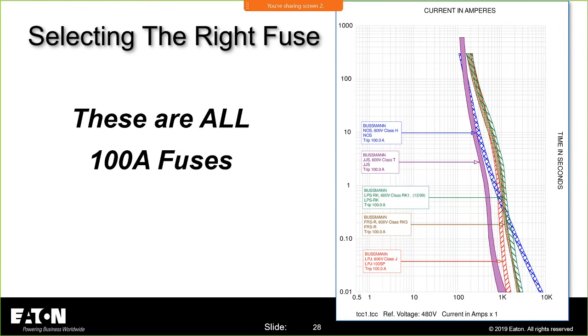All right, so let's take a look. These are all 100 amp fuses, and you're going to say, wow, those are all rated 100 amps. Yes, they are. Remember we talked about that 10,000 amp interrupting rating Class H fuse, which was non-current limiting. That's this one right over here. And when we say non-current limiting, look at the 100 amp fuse: it doesn't cross 0.01 seconds until way out here close to 10,000 amps. It takes a lot of current to get this device to trip in less than 0.01 seconds. The element in that fuse looks like this. Inside that fuse, this is what the element looks like. It's like one big pinch point. This is hollow in the middle, and this is your metal on either side. That's a Class H fuse.